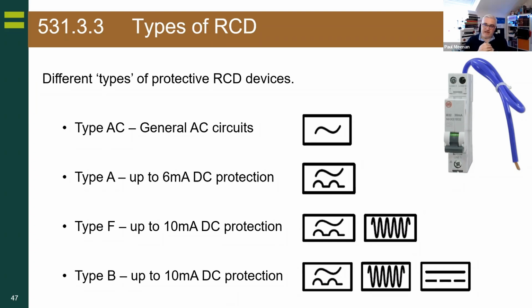I wouldn't be using AC unless I have an old bar heater somewhere. But I think in the next 5 to 10 years, Type B will be the minimum because of the utilization of DC in installations. But just be mindful, only up to 10 milliamps. If you measure more, and I have recently measured a hell of a lot more, it may not protect your installation at all. Now, when we talk about blinding and stunning, because that's what DC leakage can do, it can blind an RCD. That doesn't mean the RCD doesn't work. What it does mean is it can delay the performance of the device.